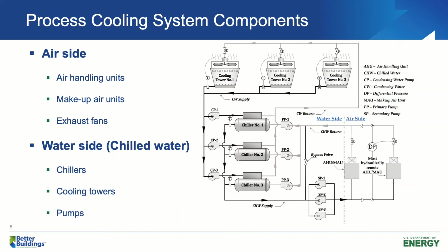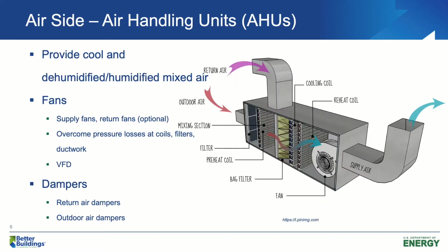What are process cooling systems? Just like I said, process cooling systems have many components and a lot of moving parts. We typically categorize these components into two groups, the air side and the water side. Both sides have three major types of equipment. On the air side, we have air handling units, makeup air units, and exhaust fans. On the water side, we have chillers, cooling towers, and some pumps.